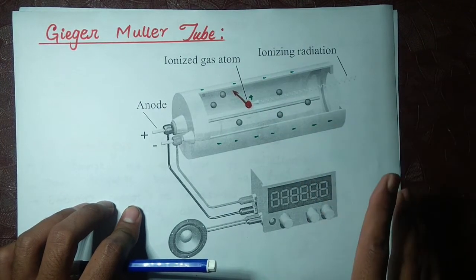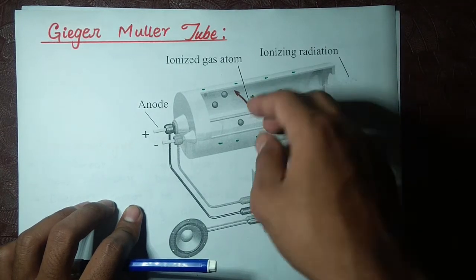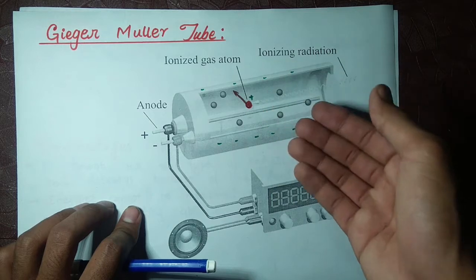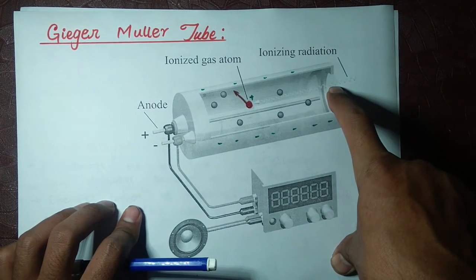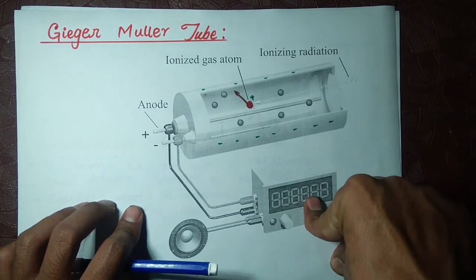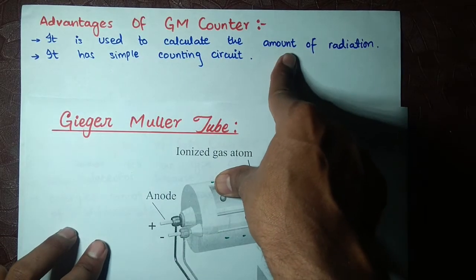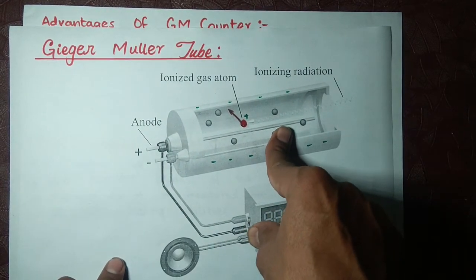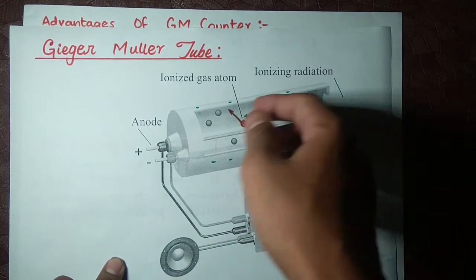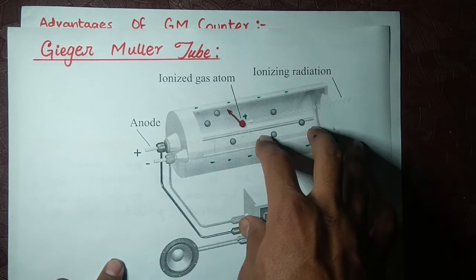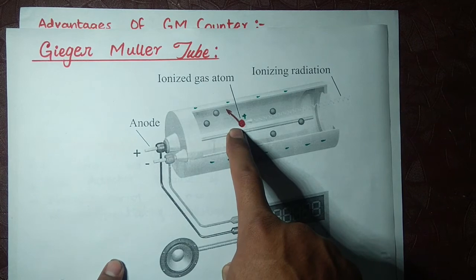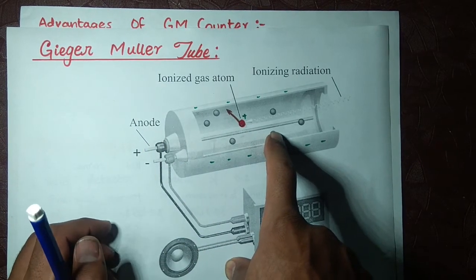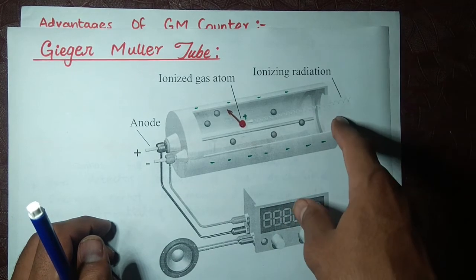One radiation comes and generates one pulse; another radiation comes and generates another pulse. Two radiations give two pulses — whether they involve two electrons, ten electrons, or five electrons. We cannot know how many electrons are involved. We can only calculate the number of radiation events from the pulses, but not the type. If gamma makes a pulse from 10 electrons and beta makes a pulse from 20 electrons, both give one pulse each — we cannot distinguish between them.